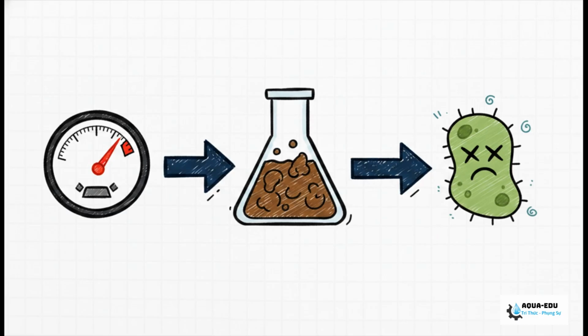But honestly, the real danger is downstream. A sustained pH shock, we're talking anything under 6.0 or over 8.5, will totally inhibit aerobic enzyme activity and kill off those sensitive microorganisms. This basically slashes your actual sludge age, forcing you to choose between seeding new sludge or risking some severe effluent standard violations. Look, this isn't just a minor sensor blip, it is a total process threat.